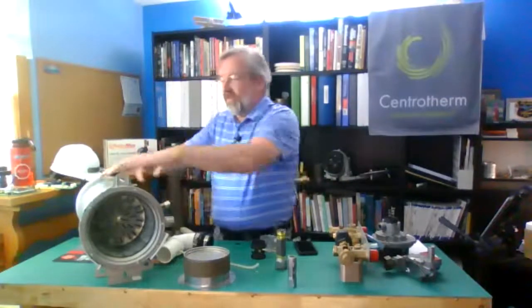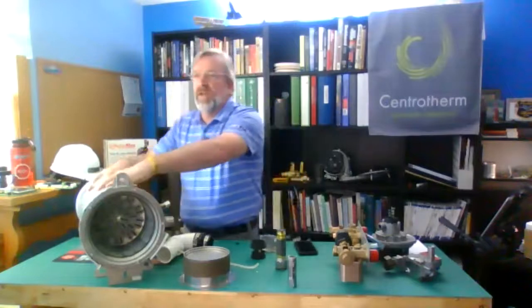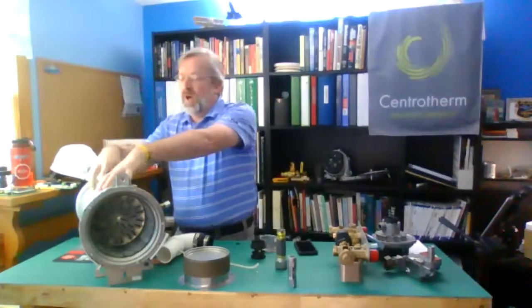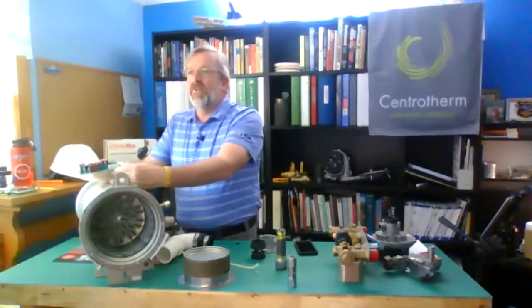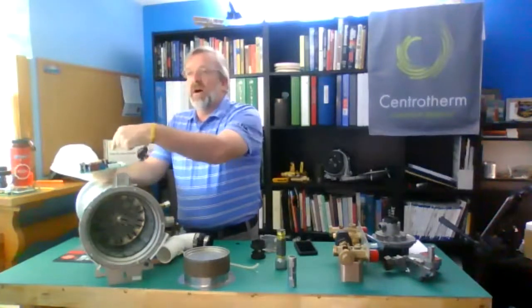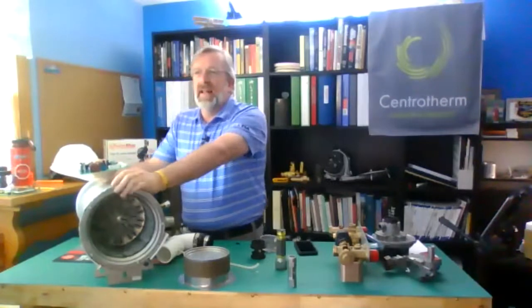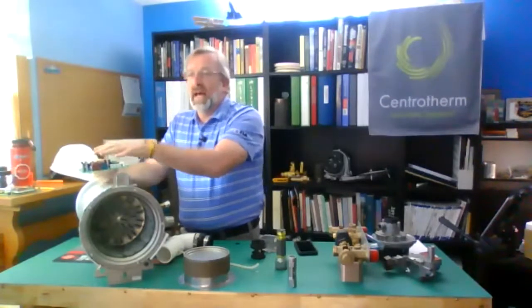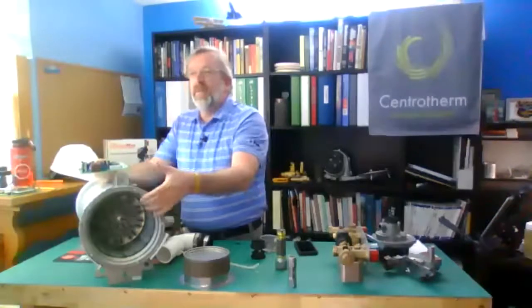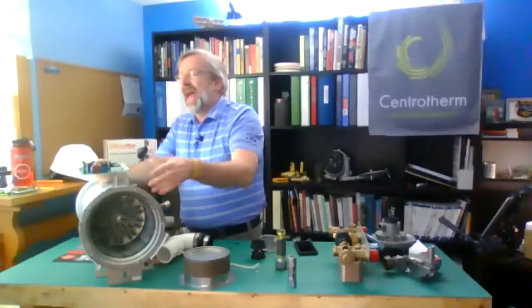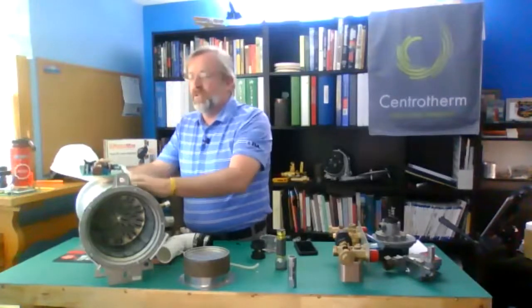Now, be cautious when doing that. This is the front side, if you will, of the boiler when it's hanging on the wall. You know what's mounted right to the front side? Yeah, it's this guy, my control board. So pouring water on my control board would be an inherently bad idea. You really want to be careful doing that. You don't need high pressure. You don't need a hose. I have seen some guys use a bug sprayer, a little pump sprayer, and they get in there and spray it out with that.